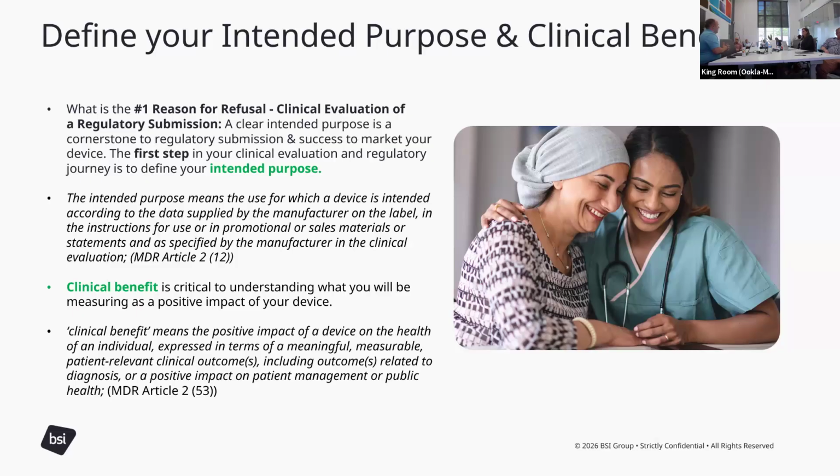The other thing we see, especially for software devices, with AI being the hot trend right now: devices have to have a clinical benefit to the patient. We see a lot of devices talked about that aren't actually medical devices because they don't have an intended clinical benefit that you can actually articulate, or it's not a clinical benefit that's actually relevant to a patient.